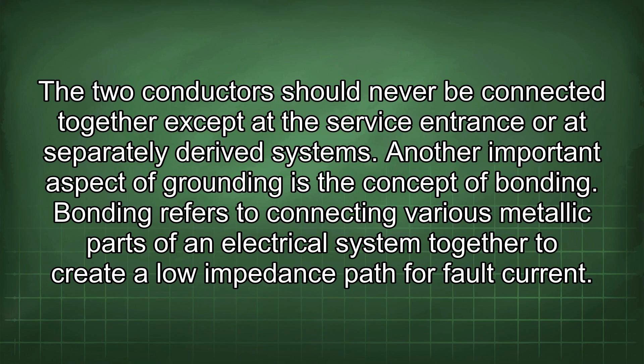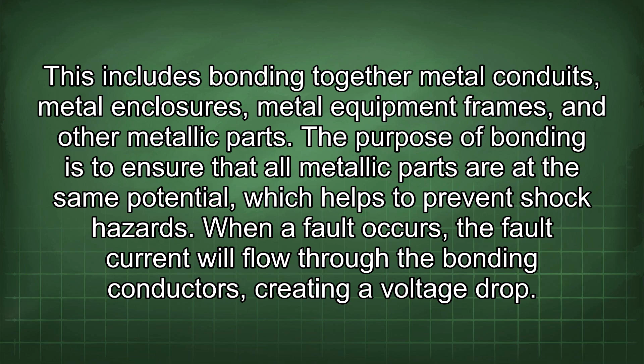Bonding refers to connecting various metallic parts of an electrical system together to create a low impedance path for fault current. This includes bonding together metal conduits, metal enclosures, metal equipment frames, and other metallic parts. The purpose of bonding is to ensure that all metallic parts are at the same potential, which helps to prevent shock hazards. When a fault occurs, the fault current will flow through the bonding conductors, creating a voltage drop.